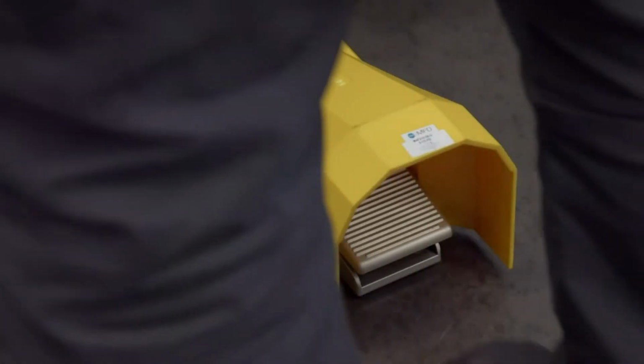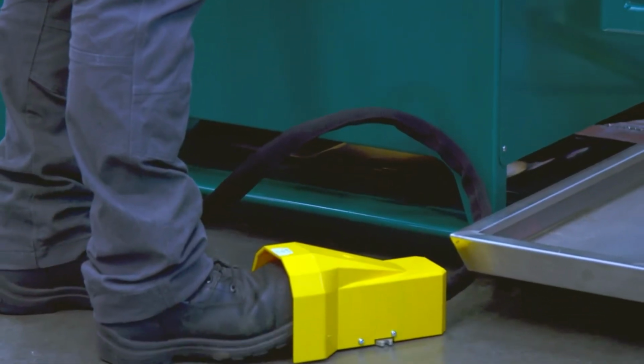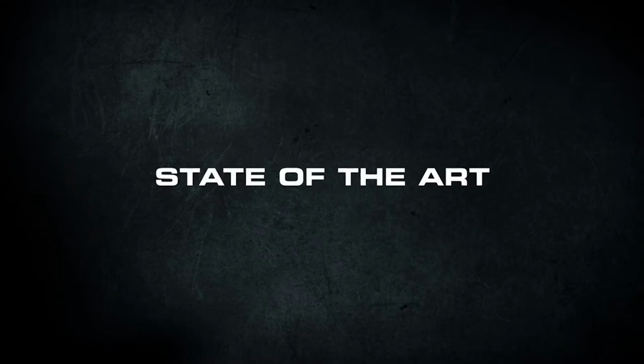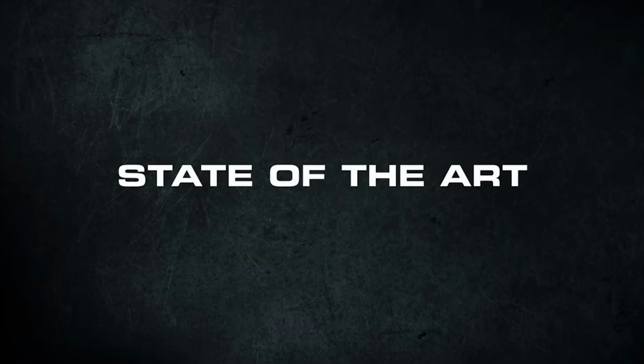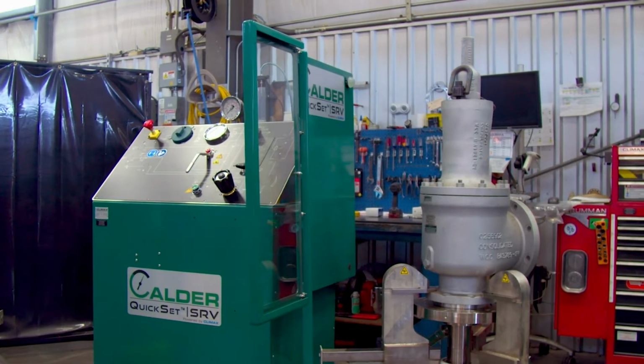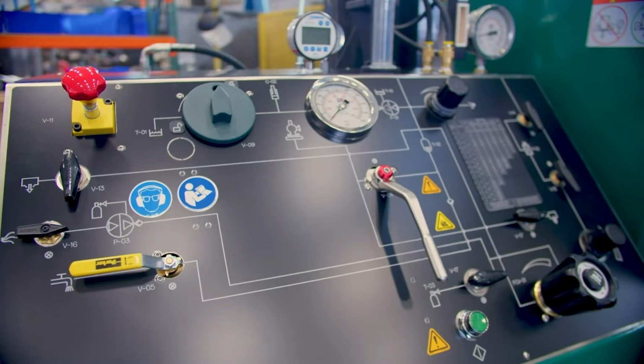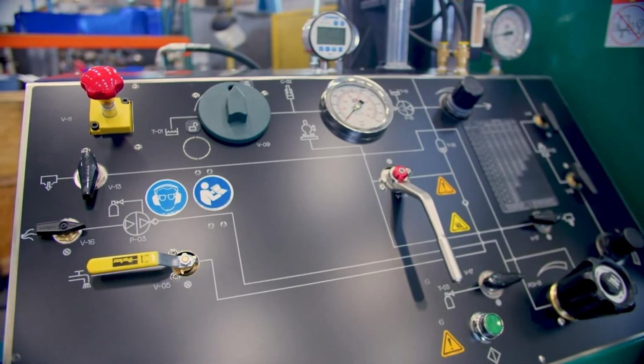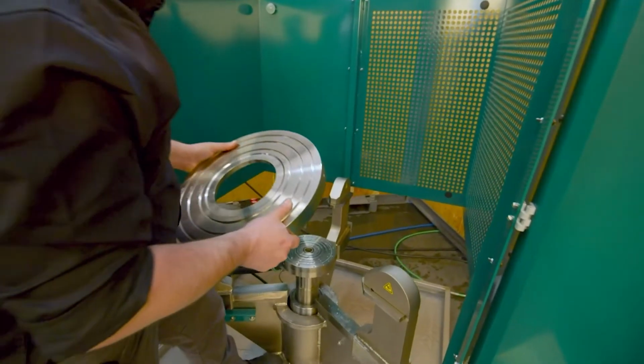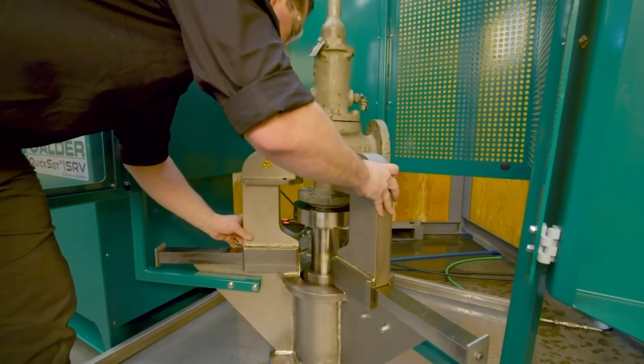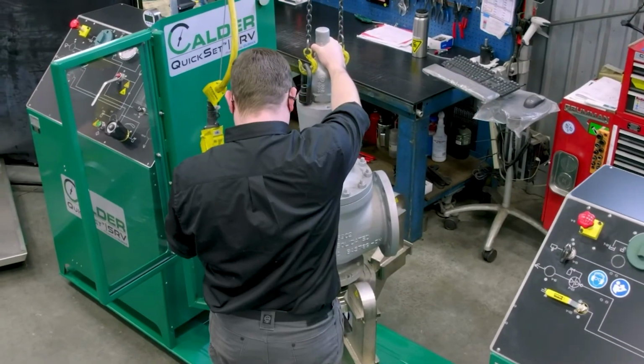User-friendly foot pedal is designed to ensure the technician's hands are free to assist with valve clamping. The unique high-flow design of the CALDER QUICKSET is field upgradable, giving the user the ability to upgrade the vessel, the tubing, the seal plate inlet, and the clamping force, allowing operators to test a larger range of valves.